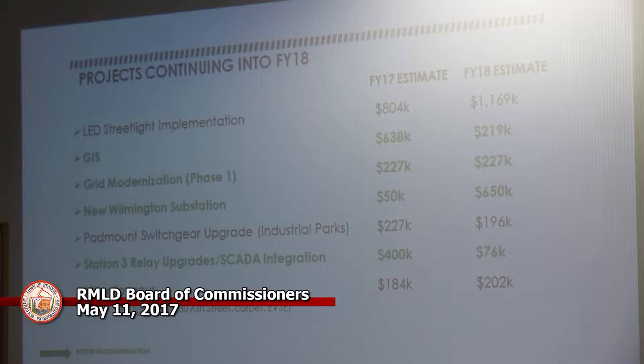Grid modernization phase one - we're still going to be installing more. We did a pilot program last year, installing 4 switches, and this year we're going to install another set of 4 switches to program. We've already started seeing the benefit of installing these, and grid modernization is something all utilities across the state are pursuing in order to improve reliability. We actually saw the benefit of that during the last storm, when the feeder was picked up in less than 10 seconds.